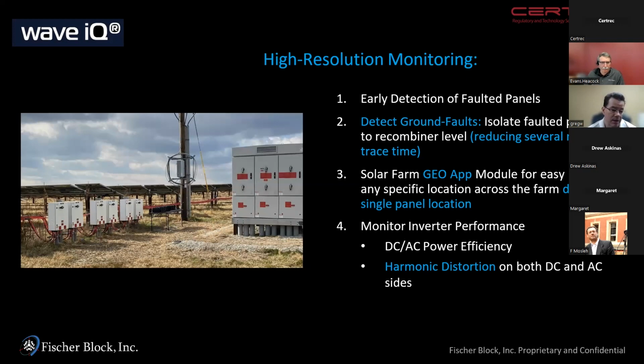And so this is on an implementation at a solar farm. I just happened to be at the solar farm this week, yesterday and the day prior, and it's interesting because some people say, well, what is there really to measure on a solar farm? It's all DC, just flat line voltages and currents. However, it's very interesting when you do the high resolution monitoring, the frequency distortions that exist on a solar farm and near the inverter with the harmonic distortions and even ground faults. They happen very quickly. Those are transitory events.